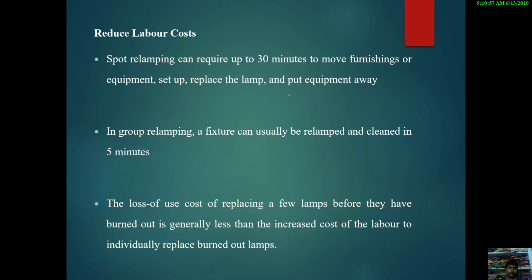Reduce labor cost: spot relamping can require up to 30 minutes to move furnishings or set up equipment to replace the lamp and to put the equipment away. When we consider group relamping, the fixtures can usually be relamped and cleaned in 5 minutes, so the time is also saved when considering group relamping. The loss of use cost of relamping, that is replacing a few lamps before they have burned out, is generally less than the increased cost of the labor to individually replace burned out lamps.